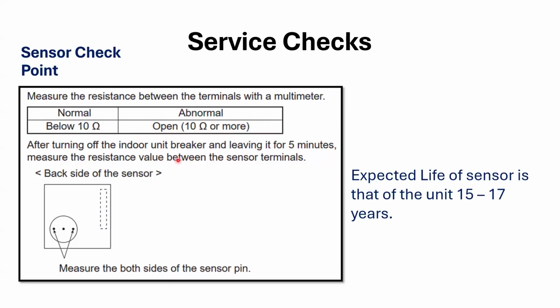So after turning off the indoor unit breaker, leave it off for 5 minutes, then measure the resistance between the sensor terminals. Like I say, I always disconnect for any ohm testing, disconnect it from the board, because it can pick up resistance through the board and throw the reading off. So expected life of the sensor is 15 to 17 years. That's pretty good. We will see, right? It's one of those sayings, time will tell.